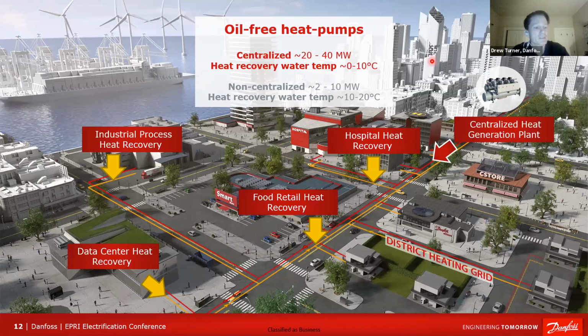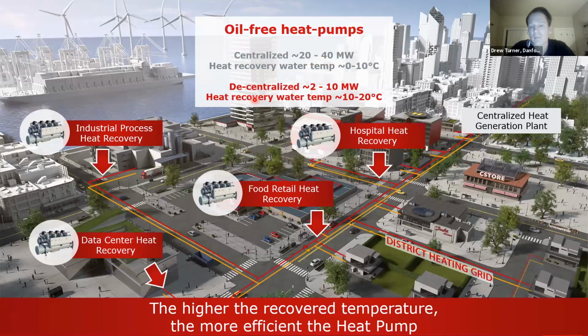As I mentioned, there are several reasons for that. The technology is optimized for that. If you focus on district energy especially, and you focus on water-to-water heat pumps, that in turn drives you toward the more distributed. I've seen a lot of publications about the move from centralized to distributed heat pumps as a part of these district energy systems. The reason for that is that as you move out in the grid away from a central generation plant to the more distributed, you also move up in general in the heat recovery temperature, because you're recovering the heat off those symbiosis applications where you're providing both the cooling and the heating. That in turn means a more efficient heat pump.